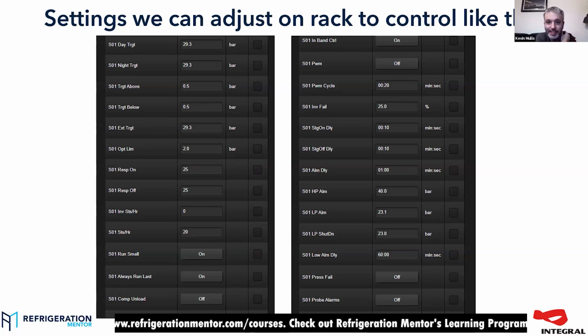So we always run last quite frequently. When it hits the pressure called LP shutdown, it will stop the compressor anyway. But as you can see, LP shutdown is a ways lower than the target. As soon as it sees some load again, it will start regulating back in the normal way. But it will just sit there with the VSD at minimum until it hits the always run last set point.